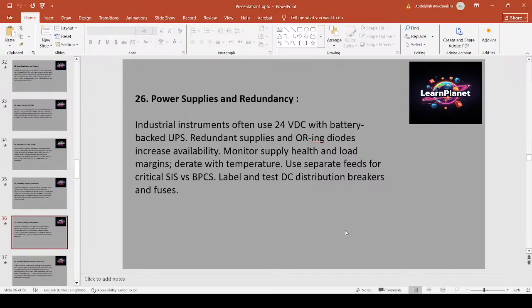Power supplies and redundancy. Industrial instruments often use 24 VDC with battery-backed UPS. Redundant supplies and OR-ing diodes increase availability. Monitor supply health and load margin. Derate with temperature. Use separate feeds for critical SIS and BPCS. Label and test DC distribution breakers and fuses.